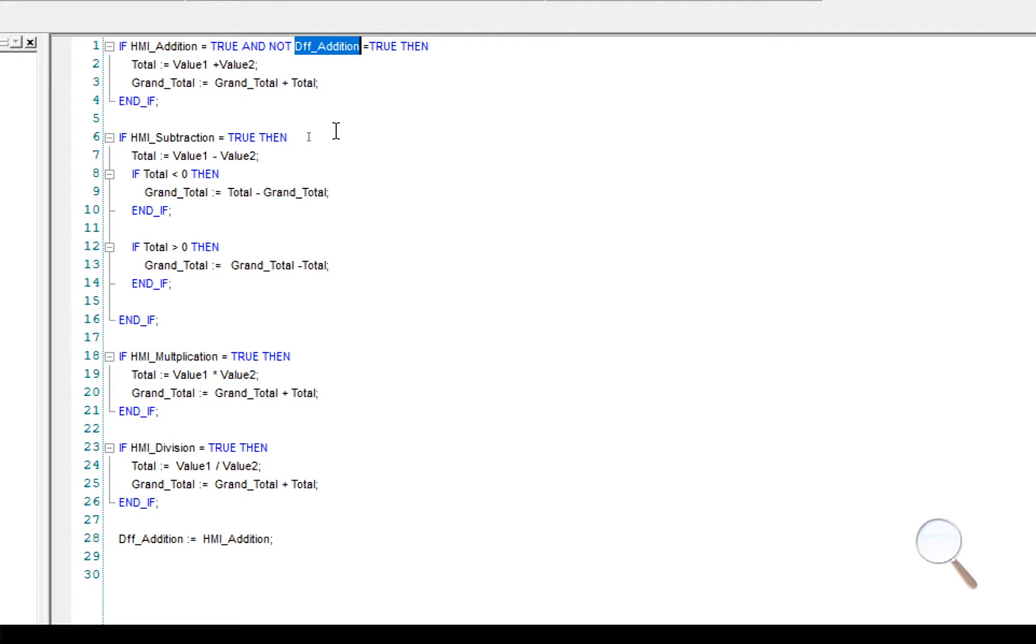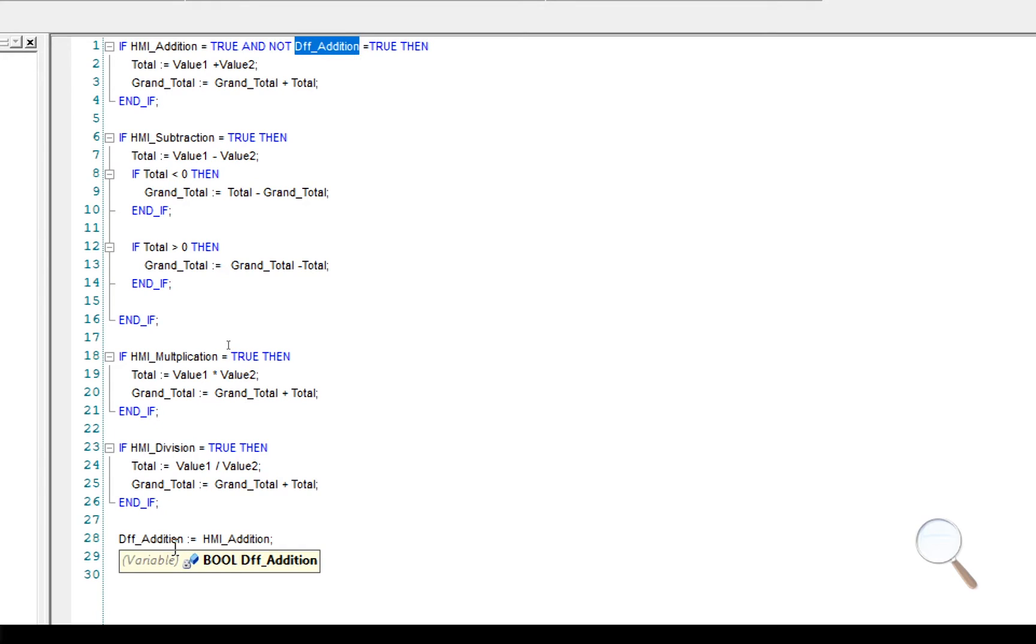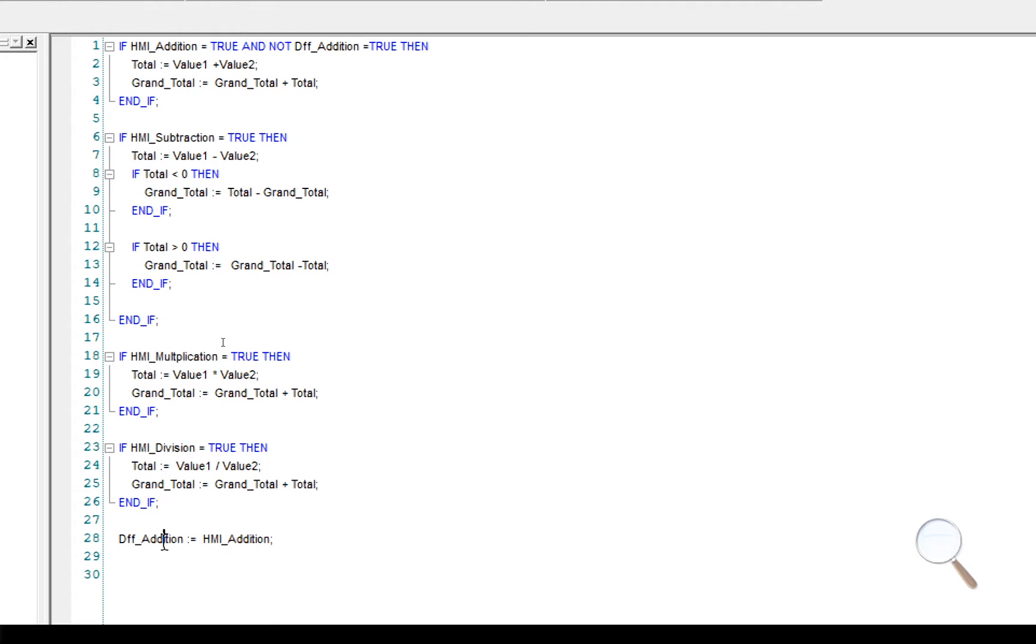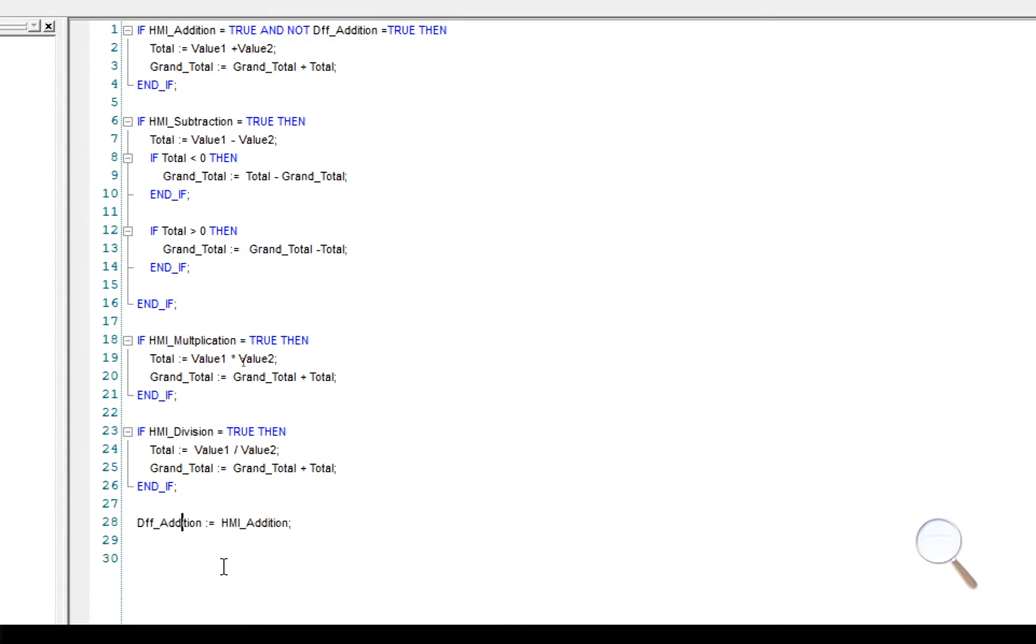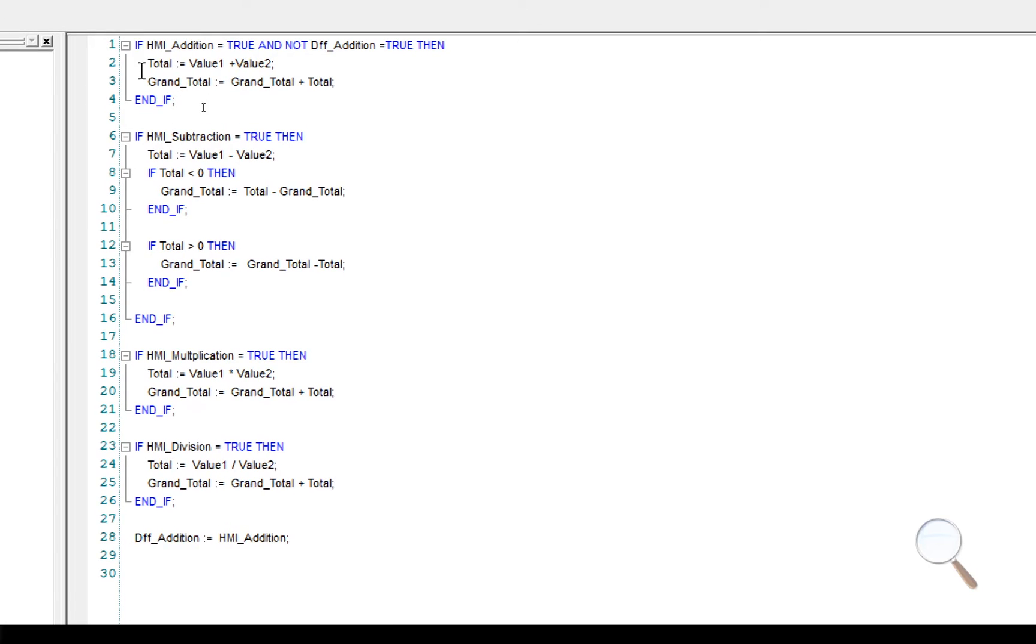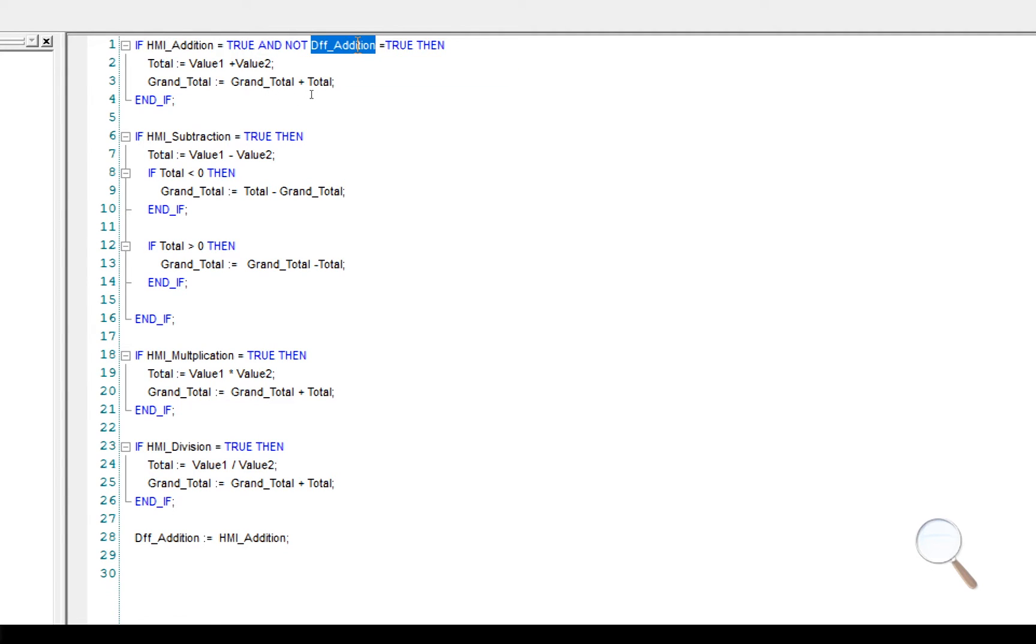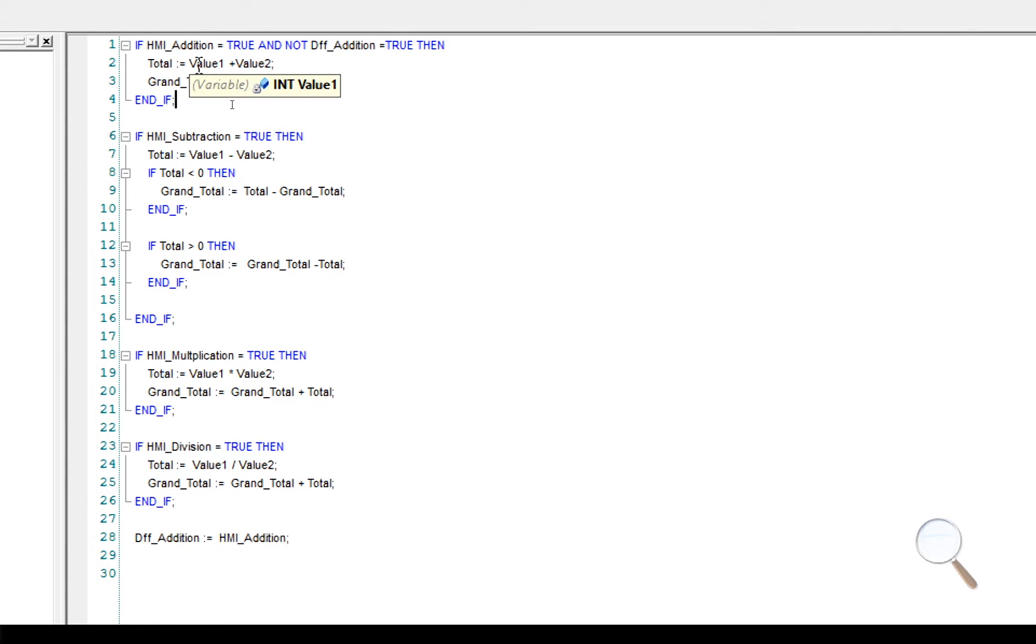When I press this button, HMI addition will be equal to true. And diff addition will not be equal to true. So this code will run. The program will attempt to run the rest of the code until it gets to the end, at which point it will set diff addition equal to the same value as the HMI, which will be one. The code will cycle and come back to the top, at which point HMI addition is equal to one because you're still pressing the button, and diff addition is equal to one, so it won't run this code. So effectively you've created your own differential function. That is, this code will only run through one cycle.